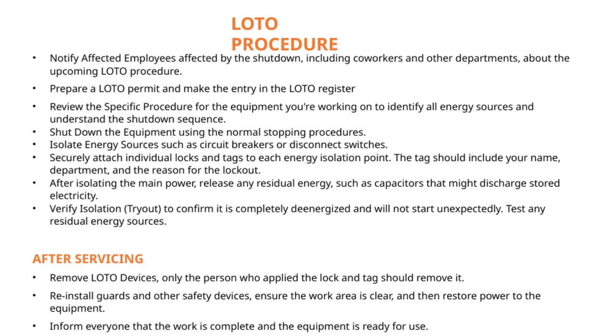Once the equipment is off, isolate all energy sources. This means disconnecting circuit breakers or switches that supply power to the equipment. It's important to do this thoroughly to prevent any accidental energization.